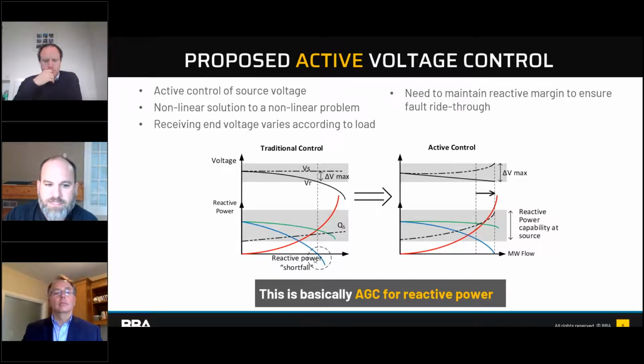But the question is whether that's actually a reactive power shortfall, or just a limitation because you ran out of delta V, out of voltage headroom to deal with the contingency, when you'd recover just fine. From the system's perspective, 0.8 can be a very healthy voltage. It's your equipment that gets broken, and people connected to the system who don't like it.